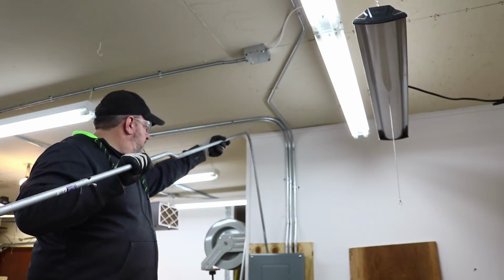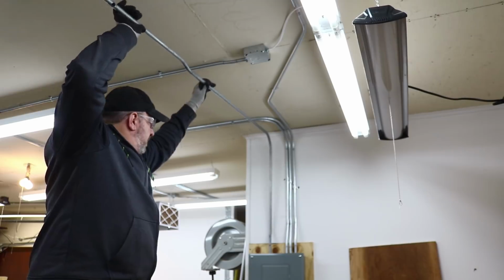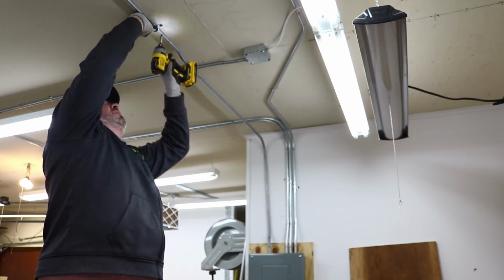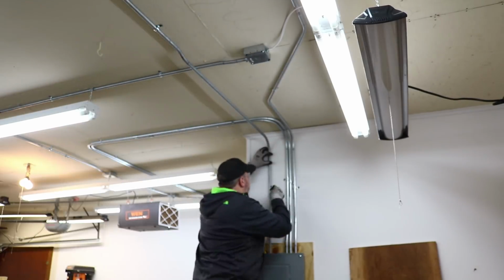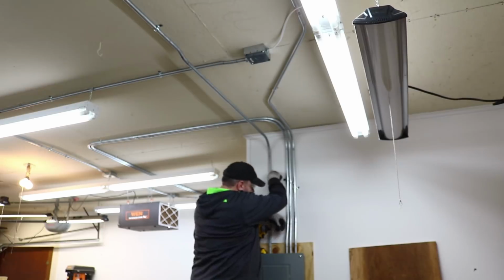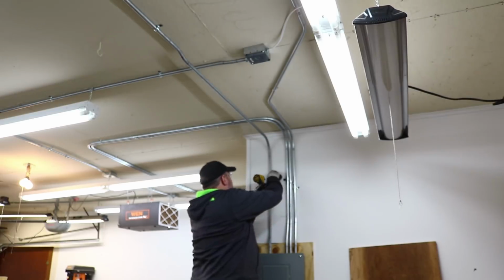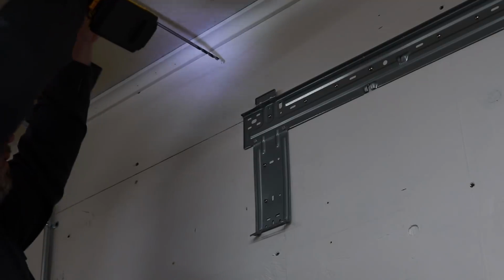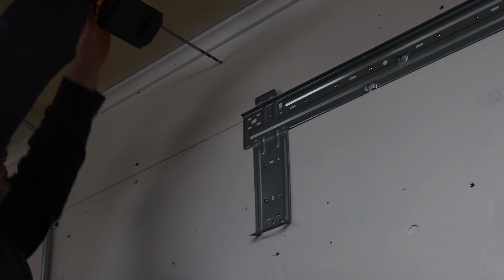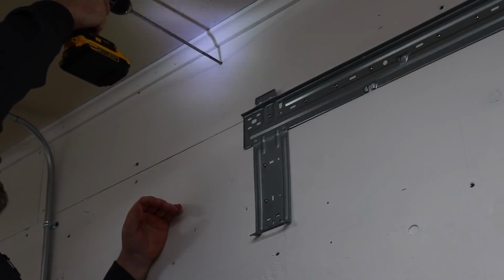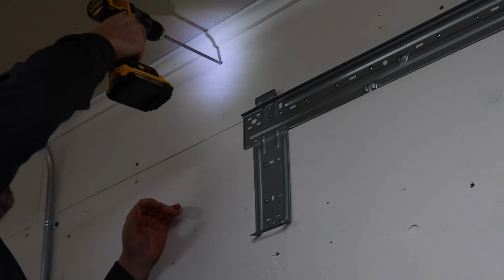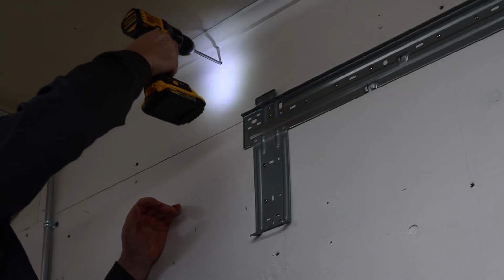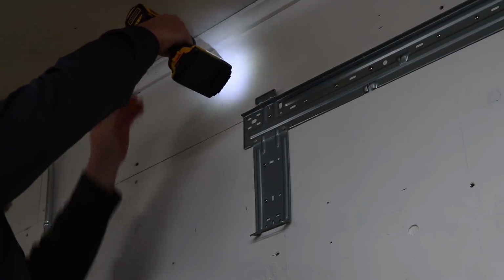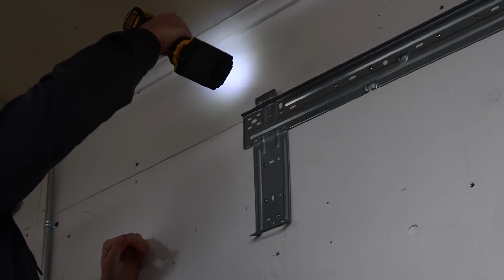Once I got the connector in the panel, I could go ahead and attach the EMT to the ceiling to get it placed, and then I could run the other half from the other direction. Before I could install the other half of the EMT on the ceiling, I needed to make the penetration through the wall that would accept the galvanized nipple that would lead down to the disconnect box.